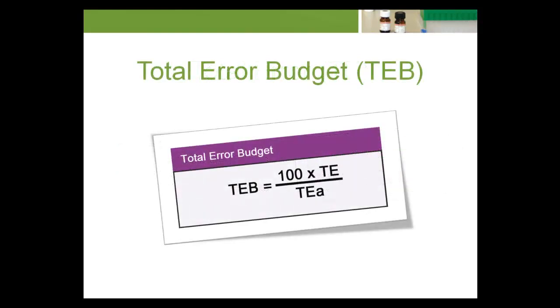The total error budget, TEB, is a quantity that relates the laboratory's test system process capability, TE, to the laboratory's quality requirement, TEA. TEB equals 100 times TE divided by TEA. TEB reflects the percentage of the TEA in patient results that is consumed by the laboratory's inherent test system imprecision and bias. How large can TEB be before a lab should be concerned that its test system capability is not well aligned with its quality goals?